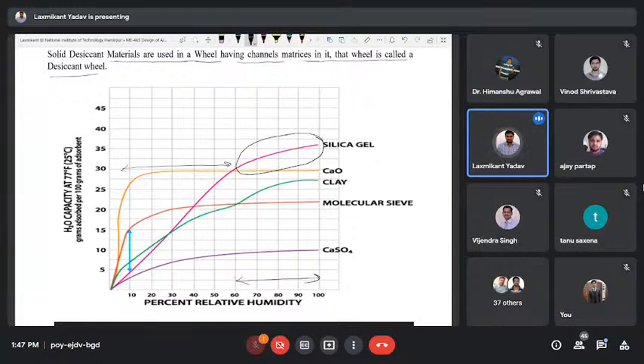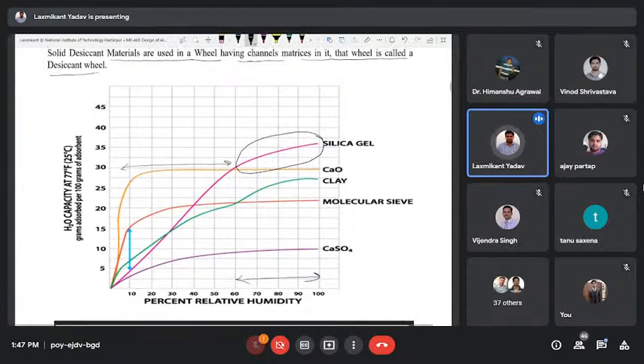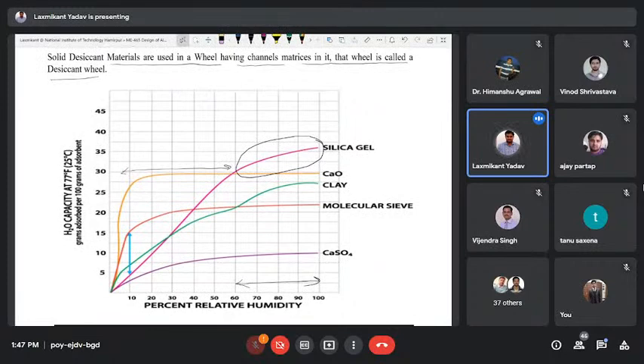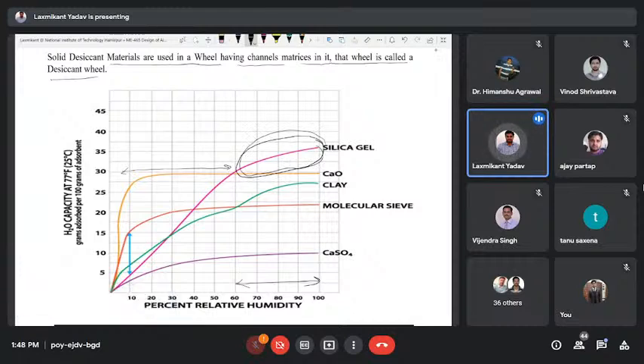So we will categorize these desiccants in the next slide. That is based on its structure, that is, the diameter of the capillary. Higher surface area means lower capillary volume. Similarly, higher capillary volume means lower surface area. So both are inversely proportional. If a desiccant has higher surface area, then its pore volume will be lower. Conversely, if the pore volume of the desiccant is higher, then it has a lower specific surface area. So on the basis of that, we will categorize. The desiccant having higher pore volume works effectively in the higher humidity range, and the desiccant having higher specific surface area but lower pore volume works in the lower relative humidity.